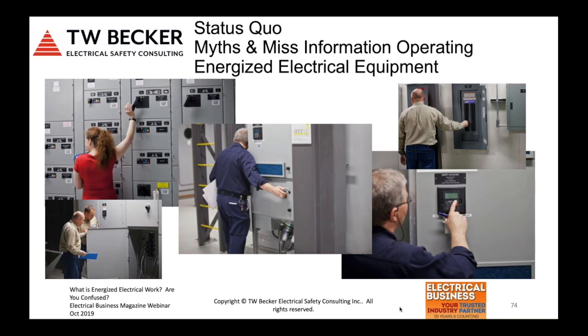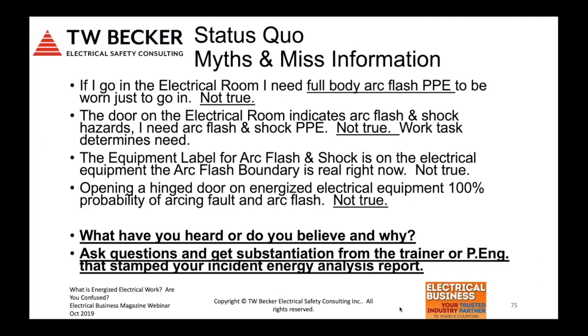All right, so just again, one of the myths that I'm saying: operating energized electrical equipment is not 100% probability of an arc flash occurring. Next, if I go into the electrical room, I need full body arc flash and shock PPE worn just to go in. Not true. The door on the electrical room indicates arc flash and shock hazards. I need arc flash and shock PPE. Not true. The work task determines the need, based on risk assessment.